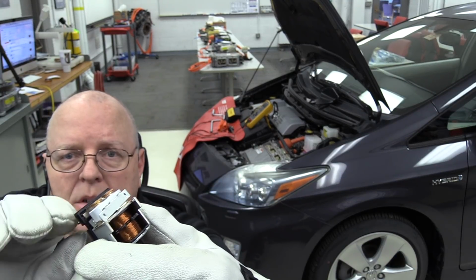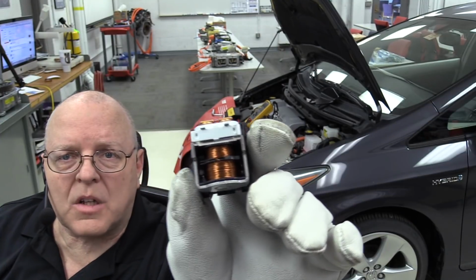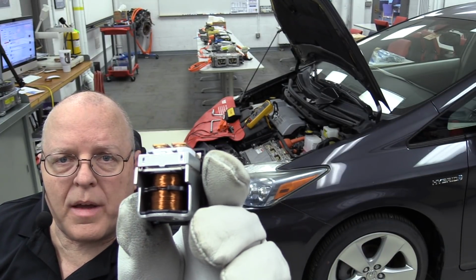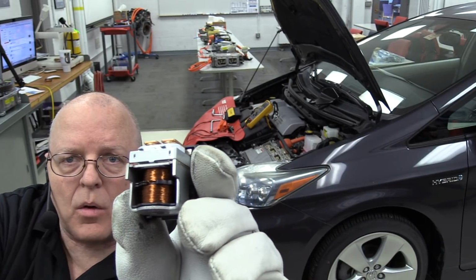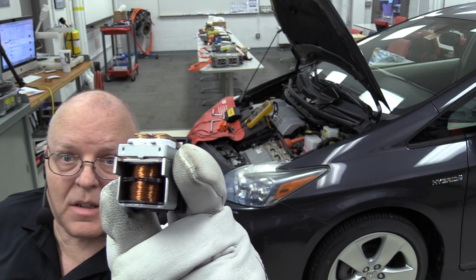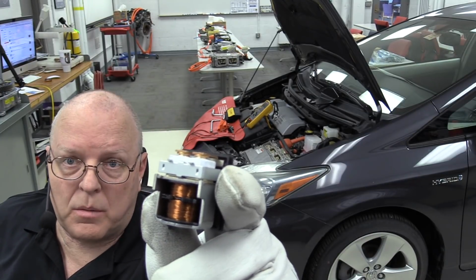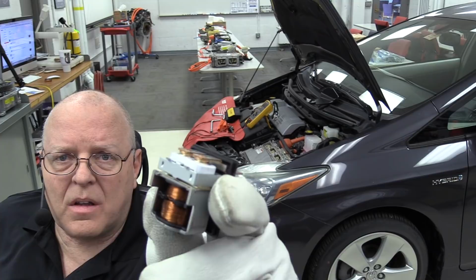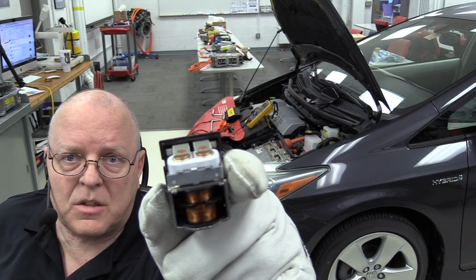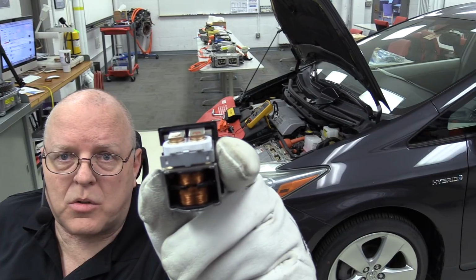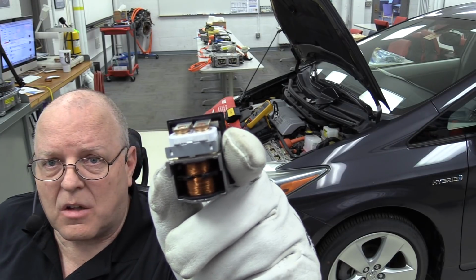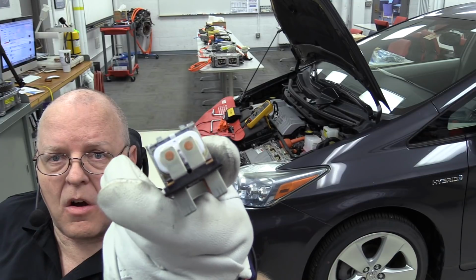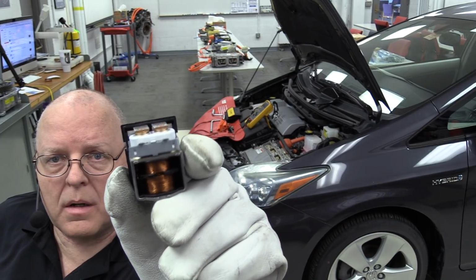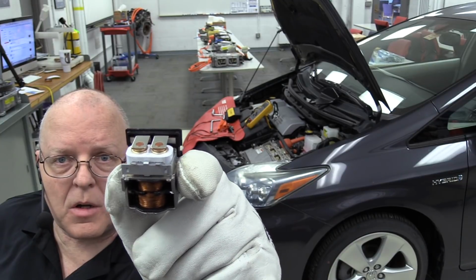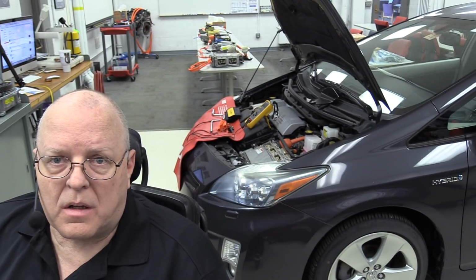block. I want you to see on the coil side of things that it has both a pull-in coil and a hold-in coil, much like a starter solenoid, which is also a contactor, and it's all hermetically sealed. It keeps oxygen and moisture away from those contacts, so they should last a long time. But that is a contactor with 2 contacts being open and closed at the same time, where if you've ever looked inside a relay, it's just 1 set of contacts opening and closing.